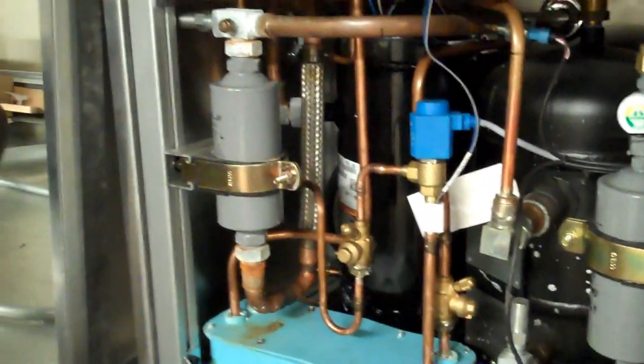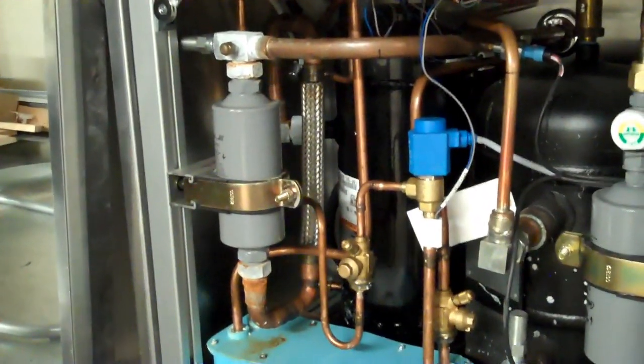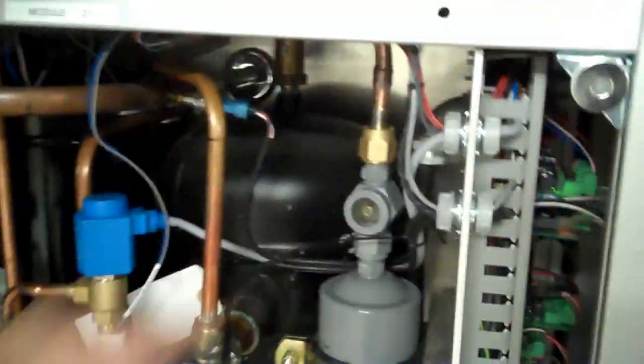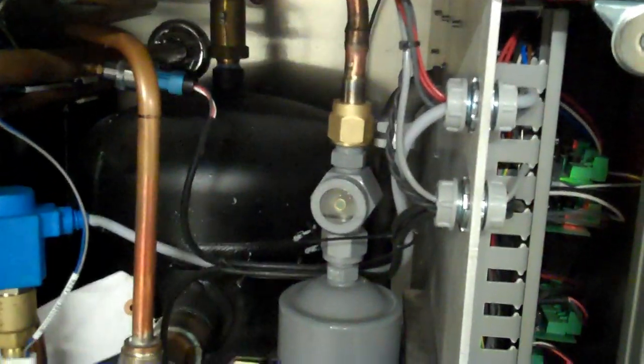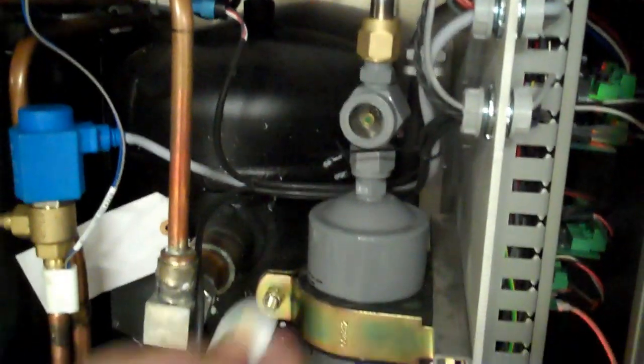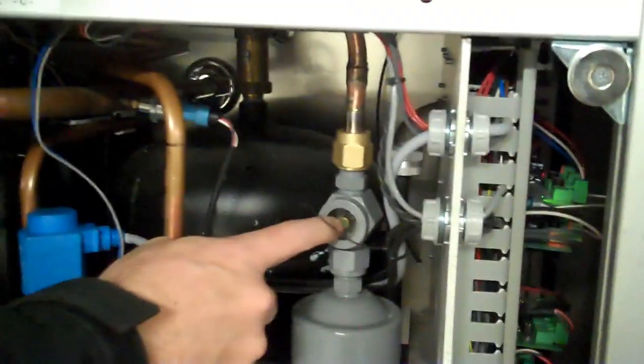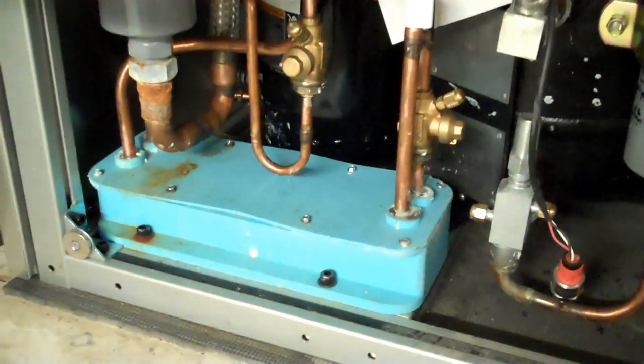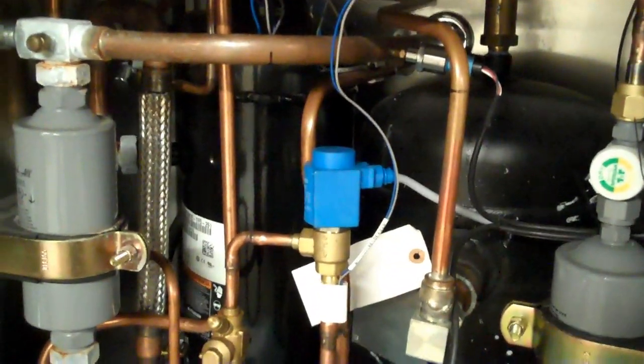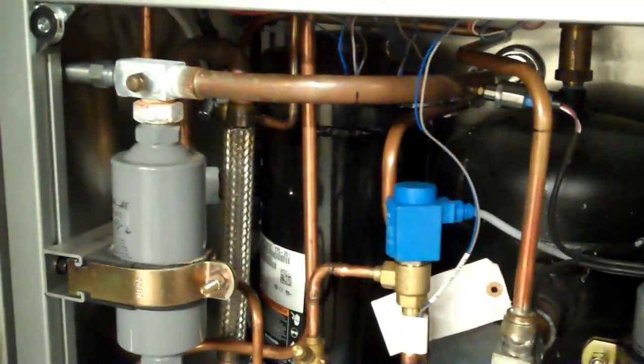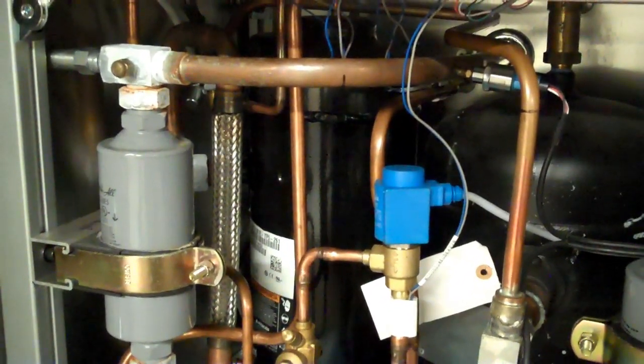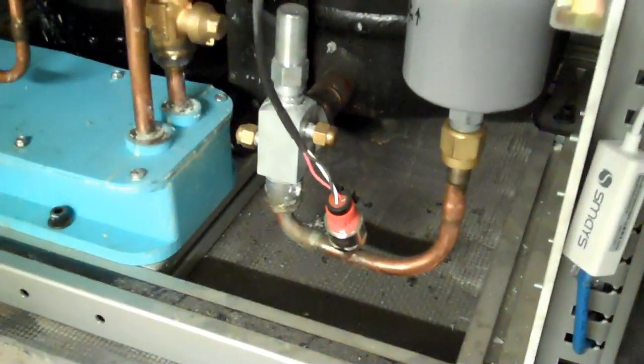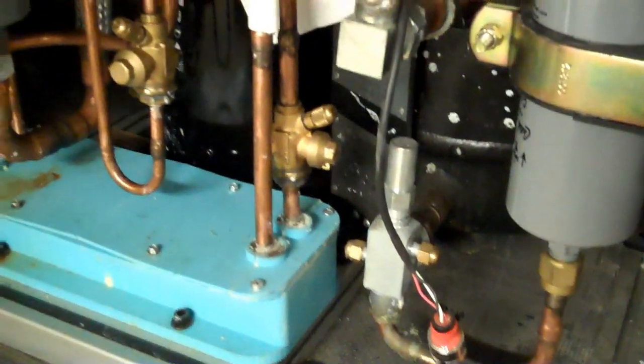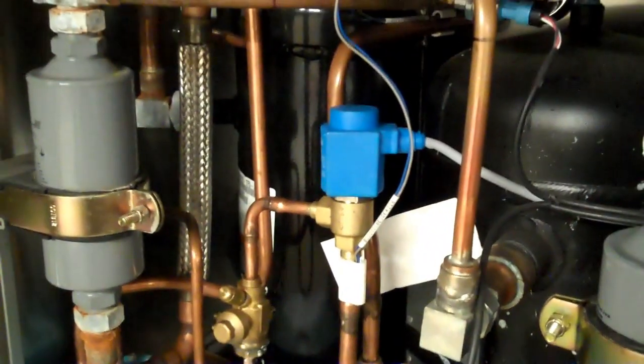The compressor's out back here, which we can shoot from this other side. When the compressor is running, you see that's the sight glass, it's full of refrigerant. Nice green color there, which is very good. And this is the subcooler. This is the electronic modulating valve to control the subcooler, which ultimately controls the discharge gas. Pressure transducers give our little computer over here all the information that gets put into the cloud.